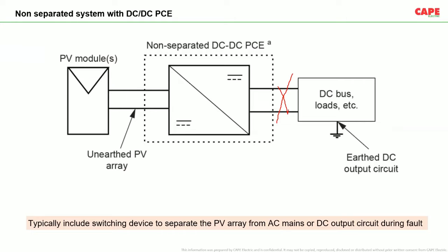So basically what I wanted to tell you is there are different combinations available, and these combinations are mainly decided by the inverter manufacturer. The inverter manufacturer will tell you what kind of system you are supposed to follow. One of the problems which I have seen is that the inverter manufacturer recommends, let's say, X topology, but without understanding the topology, a Y topology is made in the installation. This is a hazard. We are not supposed to do it. We should really understand what the inverter manufacturer intended for this particular safety measure, and we have to implement the correct safety measure. To implement this correct measure, the designer of the solar PV system has to carefully analyze and understand the different topologies which are applied along with the necessary protective measures.